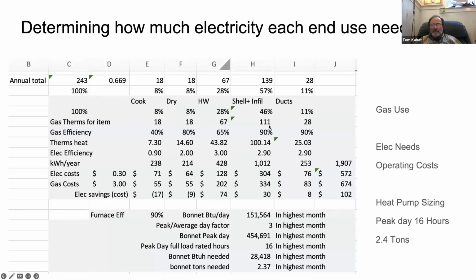There was an energy audit done that found 20% of the furnace use probably went to duct leakage, so that's the far right, 28 therms. And the other 111 therms made it into the house, keeping her warm. So that was kind of how we look at it to allocate all the gas use and figure out where it is. The next row below is just multiplying by the efficiency of each device, how efficient is each one at converting gas into heat?